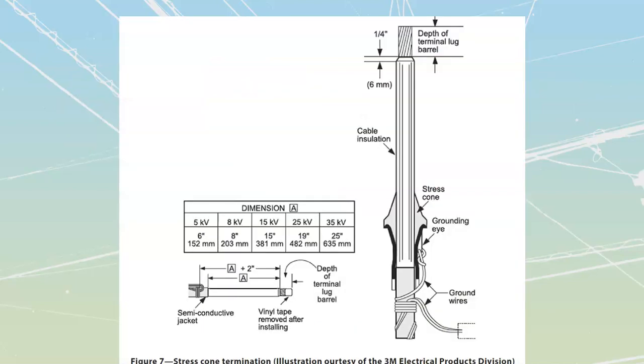All right, we're going to go through the steps on making a connection: a stress cone termination. This is for a 15 kV one, so we're going to read from inside our manufacturer's documentation. You never do one of these without fully reading the documentation first, because these are very expensive terminations, and the cables themselves are very expensive. If you screw it up, in a lot of cases you can't afford to just cut back another meter of cable. So read everything carefully, then follow those instructions.